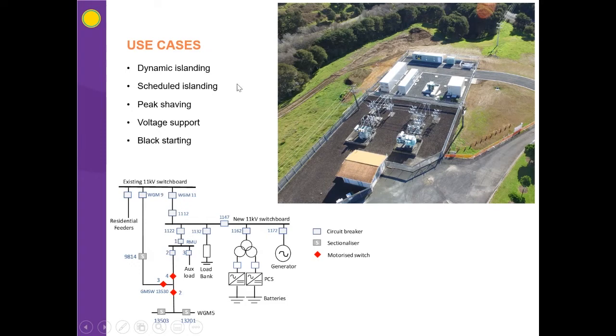Besides dynamic islanding, it's also used for scheduled islanding. Just a couple of weeks ago we had a crossarm that needed replacing on the 33 kV line, and we used the battery and the diesel to feed a substantial part of Whangamata for the time it took to do the repair. It's also used for peak shaving during summer months, during hot weather when the town is highly populated, to knock off the power peak and reduce loading on the transmission lines. We also use it for dynamic voltage support, and if absolutely necessary, we could black start using the system.